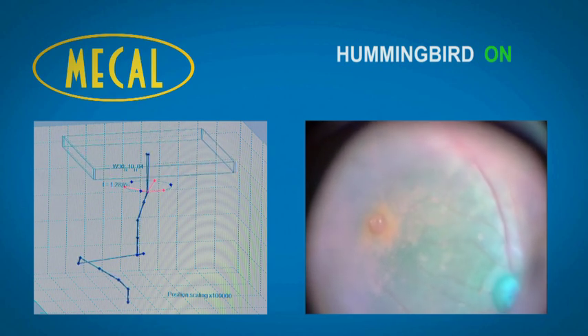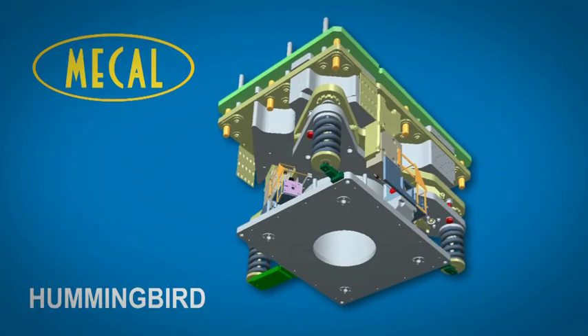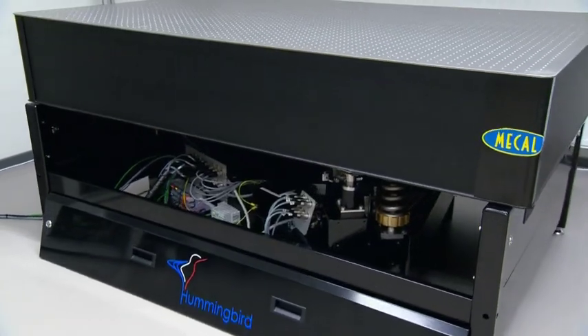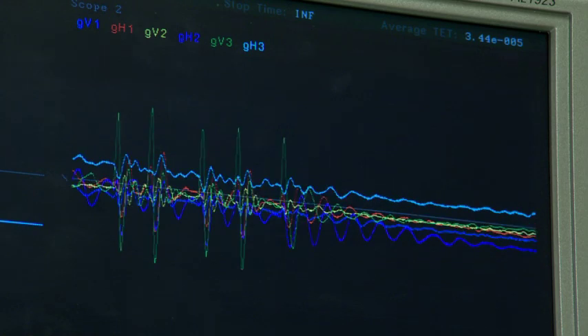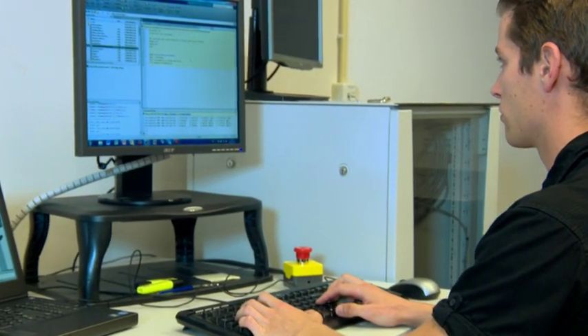Fortunately, Mecal came up with the Hummingbird. Hummingbird is an active vibration isolation technology for reducing low frequency vibrations. What we do is we measure the vibrations with the sensor and we counteract on it with the actuator. Counteracting is done 8000 times per second, and with our technology we can start reducing the vibrations from a half hertz.